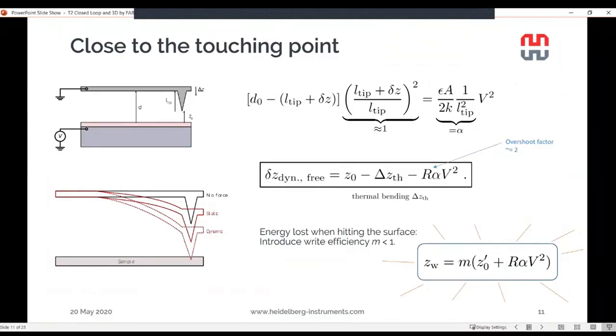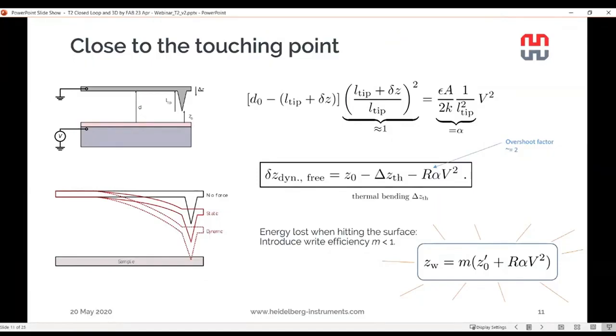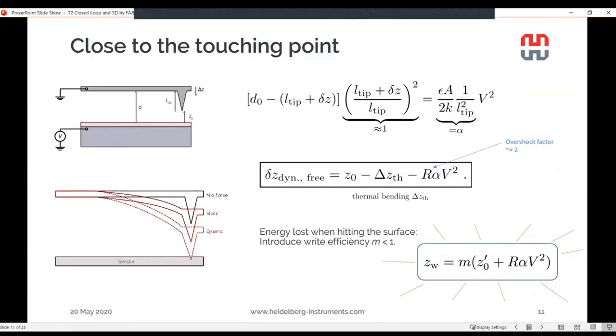and the whole system is dynamic. It goes so fast that we will see some dynamic overshoot of the cantilever. And we also have to include that with a factor that we call R. And because the quality factor of the cantilever is relatively high, this factor is almost 2. So we overshoot almost as much as we would deflect statically when we apply our force voltage. Then we also have to add our thermal bending effect that we get from the calibration.